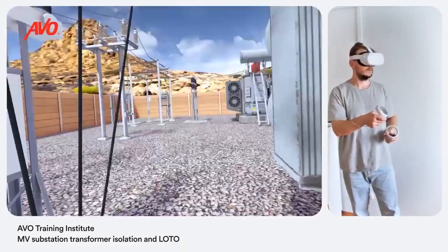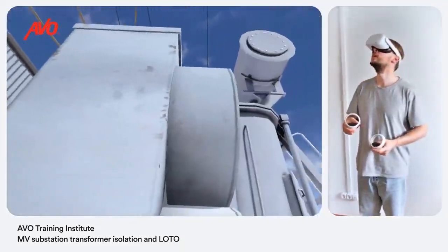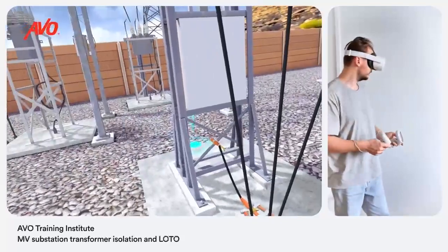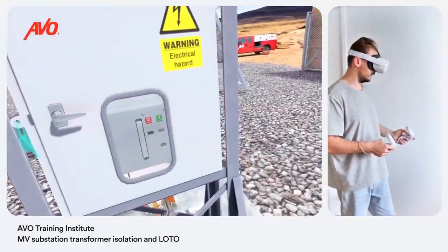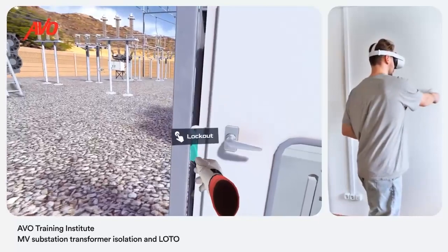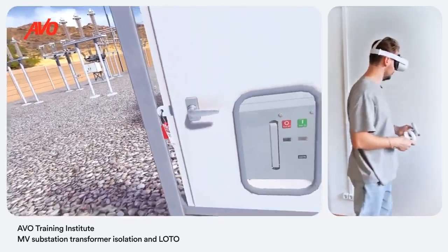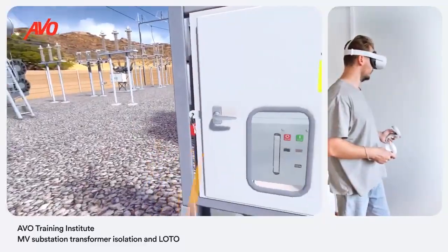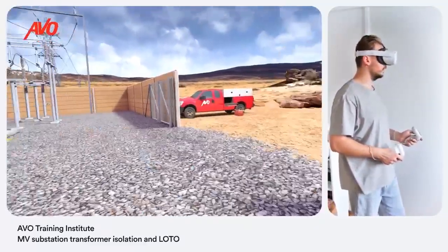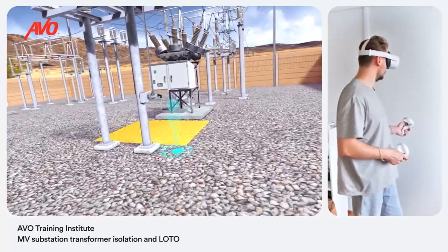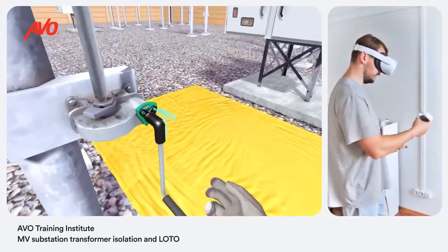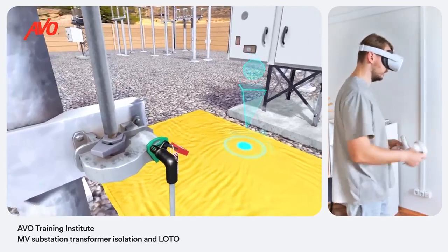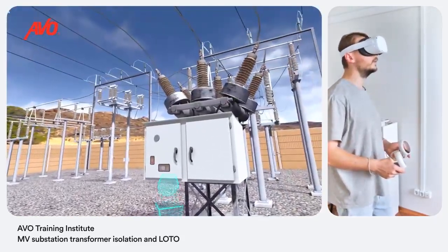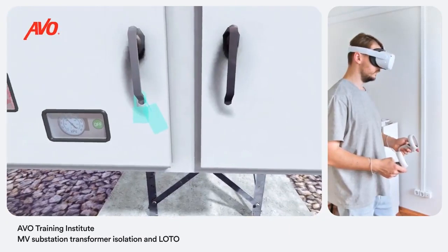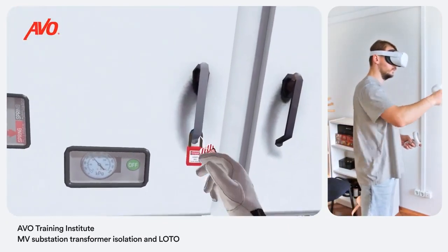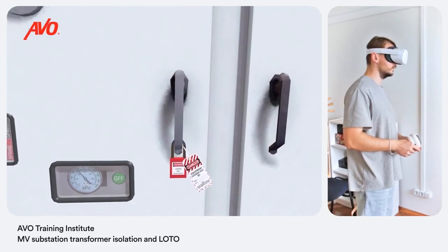Apply LOTO devices to all energy isolating devices and means. Apply a lock and a tag to the vacuum breaker. Apply a lock and tag to the group operated air brake switch. Apply a lock and tag to the feeding SF6 circuit breaker. Now, contact the control desk to confirm the procedure has been completed.